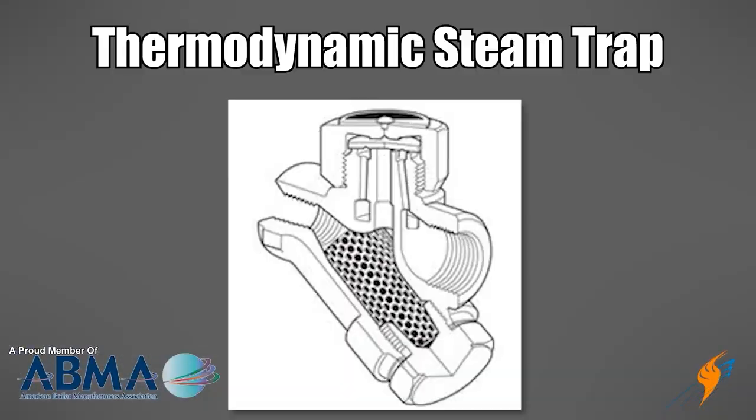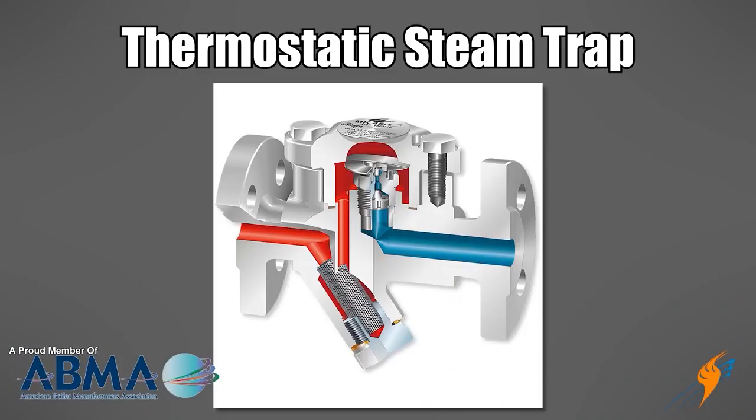And when you dump that condensate, that's what you end up doing. There are applications where there's no choice and you have to dump it, but in cases where we don't have to, we want to maximize that opportunity. Now there are ways to get the condensate to return — one of the ways is traps. We want to talk about four different types: first is thermodynamic, second is thermostatic, then there's the float, and then there's the inverted bucket.